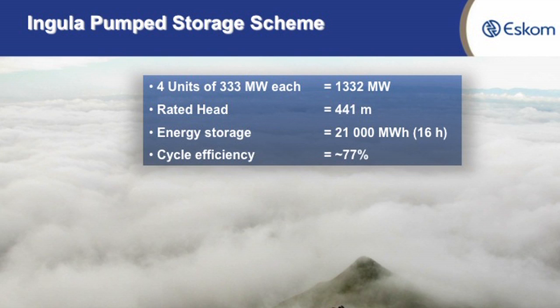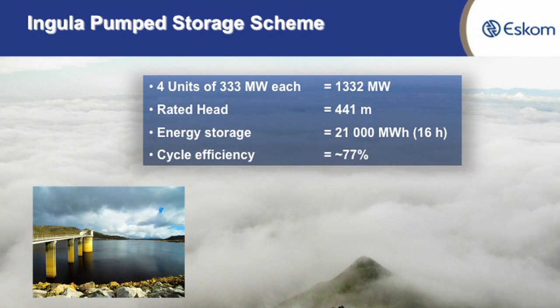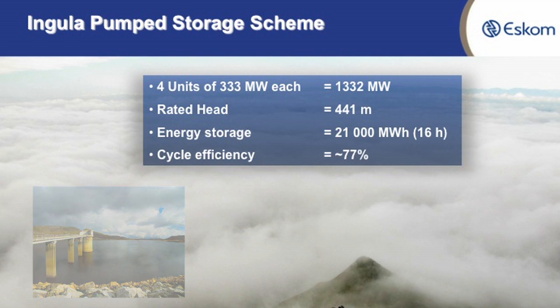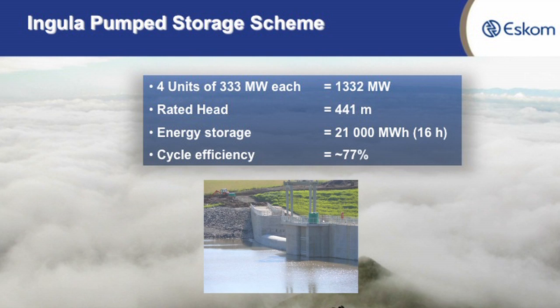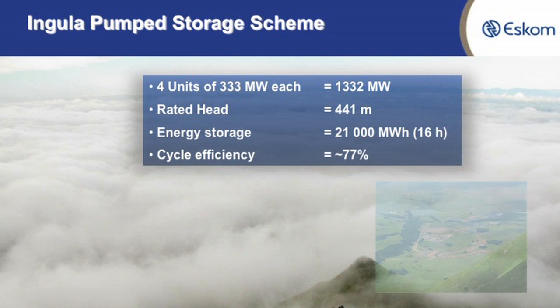4 units of 333 megawatt each, that is net power. The actual unit is 342. Rated head, we have chosen it to be 441. You can play with your rated head to decide where that optimum point is. That was 441. Our dams have the capacity of storing 16 hours of full generation of the 4 units, and a cycle efficiency of around 77. That's what we estimate at this stage. But obviously, the proof of the pudding is in the eating when we start up the machines.